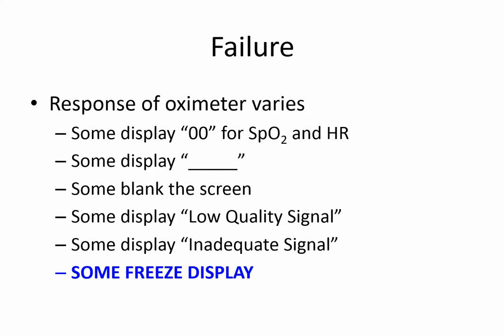If you end up with no signal, some will display double zero, some will simply display a blank screen or a line, some will display low quality signal, some will display inadequate signal, but frighteningly, one of the problems is that some will cause a freeze in the display. So you were looking at a saturation of 93%, the pulse oximeter stops working, but it continues to display 93%.